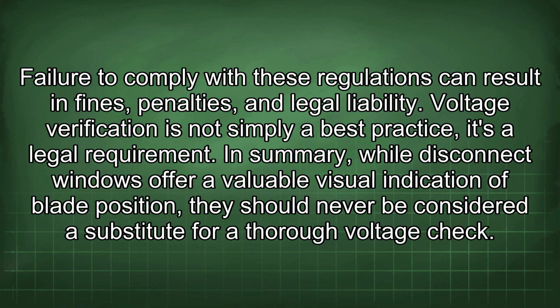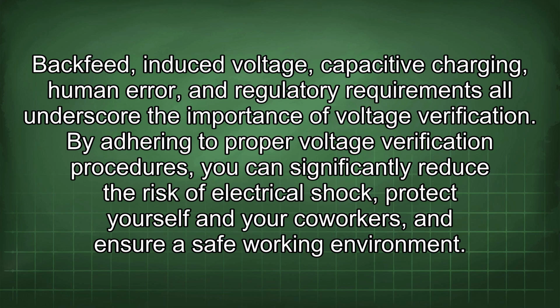In summary, while disconnect windows offer a valuable visual indication of blade position, they should never be considered a substitute for a thorough voltage check. Backfeed, induced voltage, capacitive charging, human error, and regulatory requirements all underscore the importance of voltage verification. By adhering to proper voltage verification procedures, you can significantly reduce the risk of electrical shock, protect yourself and your coworkers, and ensure a safe working environment.